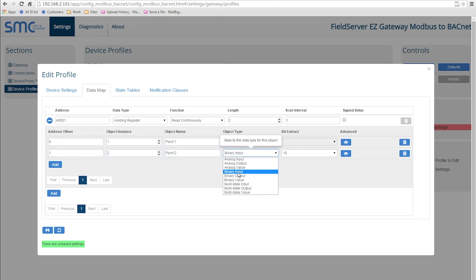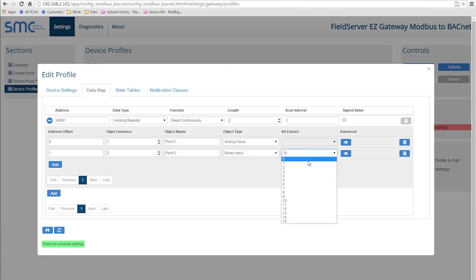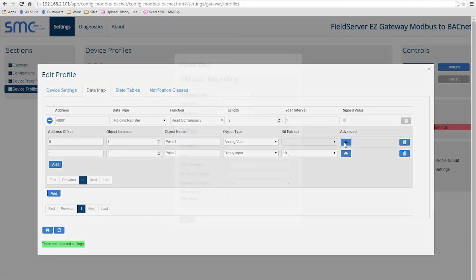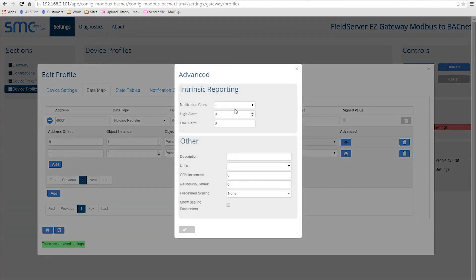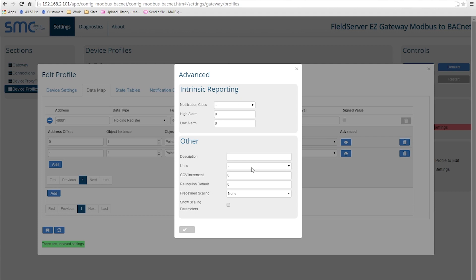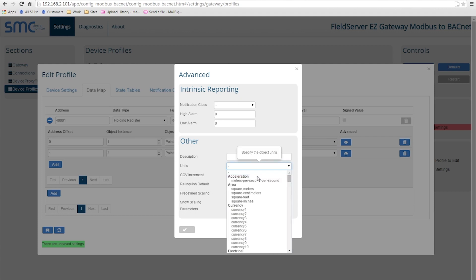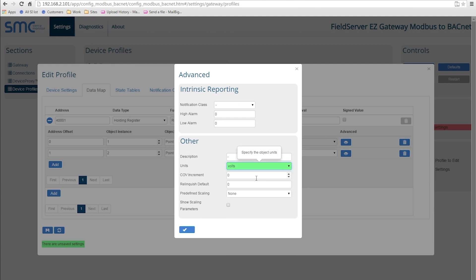You also have the ability of extracting a bit from a 16-bit register and mapping it to a binary input. There are also some advanced options which let you specify intrinsic reporting settings, adding a description to the object, specifying units, and implement scaling.